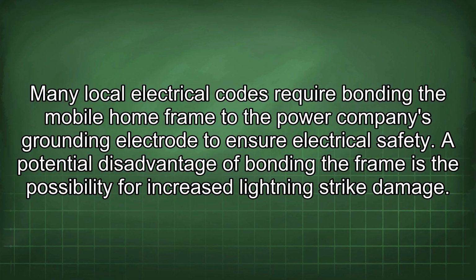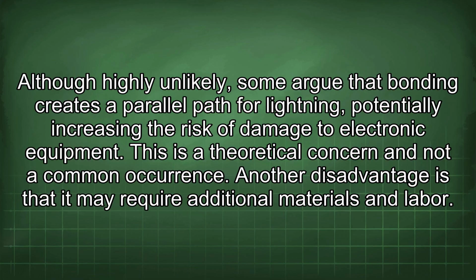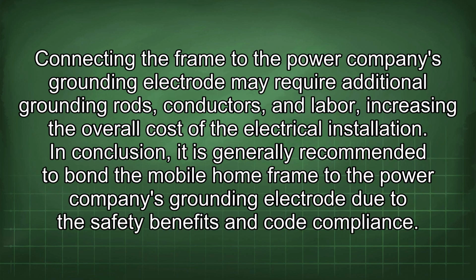A potential disadvantage of bonding the frame is the possibility for increased lightning strike damage. Although highly unlikely, some argue that bonding creates a parallel path for lightning, potentially increasing the risk of damage to electronic equipment. This is a theoretical concern and not a common occurrence. Another disadvantage is that it may require additional materials and labor. Connecting the frame to the power company's grounding electrode may require additional grounding rods, conductors, and labor, increasing the overall cost of the electrical installation.